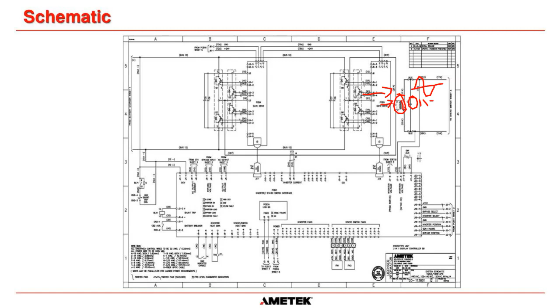Then we have our transformer here, which is just a regular isolation transformer. The windings will be designed so whatever our output is here—if this is a 120 volt system, the windings will be designed to give us 120 volts on the output. Then this capacitor, with the inductance in the transformer, smooths out that PWM waveform going into the primary into a nice, beautiful sine wave on the output that goes to our loads.